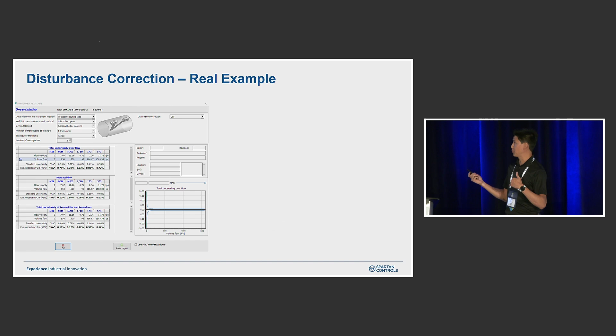So this is an example of what it would look like, here's the sizing we did. If we had perfect 10D, 3D upstream and downstream diameters, we'd be looking at around 1% accuracy. But let's say we don't have that 10D upstream, and only have 6 inches before an elbow. If you look at the accuracy there, we're about 3%. So 3%, 6 inches away from an elbow, is pretty good in my opinion.